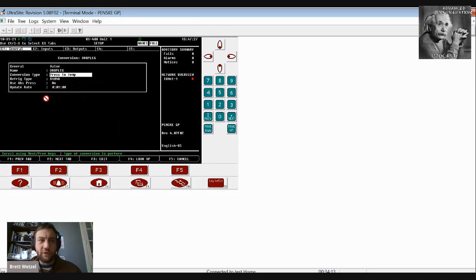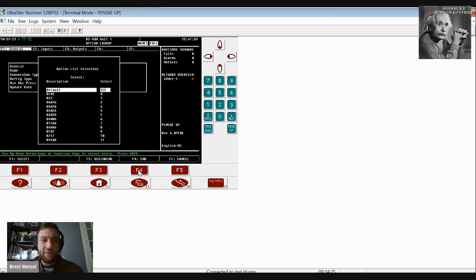So you gotta remember there's no glide on 404. But when you do select the refrigerant type, in a lot of these menus, the F4 button will actually turn into a lookup button. By hitting F4, you can scroll down here. On this particular controller, the firmware must be older because I'm not seeing the newer refrigerants with the glide. A lot of times, if you're on 407, you'll see a dew point or a bubble point or a midpoint. There are usually 3 options with the higher glide refrigerants.